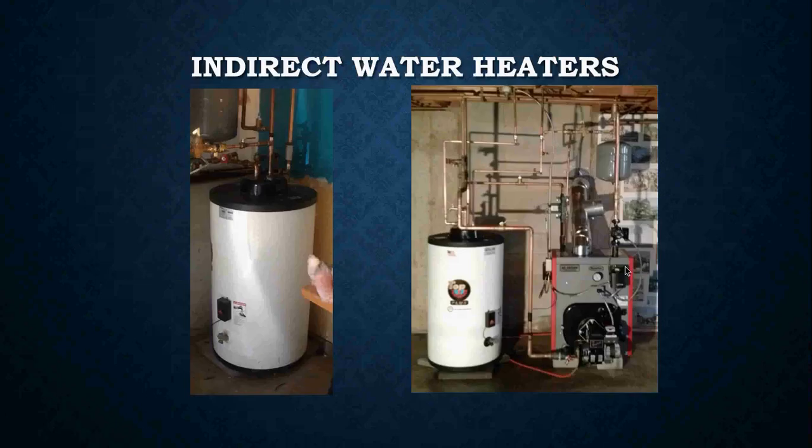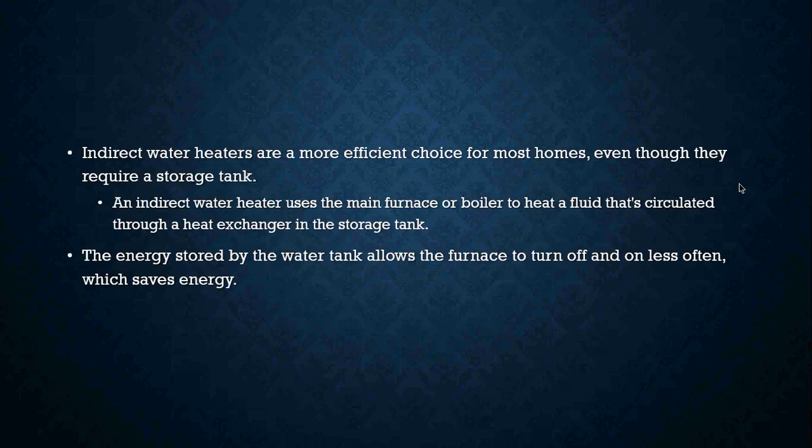But today, we go towards your indirect water heaters, where we're actually using the boiler and hot water as a separate zone of heating. Okay, indirect water heaters are a more efficient choice for most homes, even though they require a storage tank. An indirect water heater uses the main furnace or boiler to heat a fluid that circulates through a heat exchanger in the storage tank.